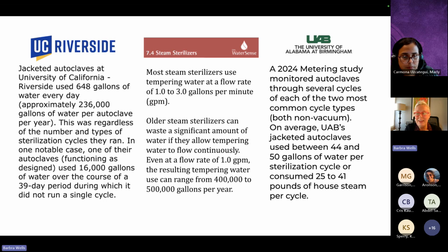This study also measured the effluent cooling water, which isn't typically part of the water required to run an autoclave cycle. So manufacturers, we don't have to report that. Remember, effluent cooling, also known as tempering or bleed water, is needed to cool the steam that's always condensing inside the jacket before it can go down the drain. Many older models use effluent cooling water continuously. For example, Stanford did an audit of their autoclaves in 2017, and they found they were using an average of 1,550 gallons of water per day each. Again, whether or not they were idle.